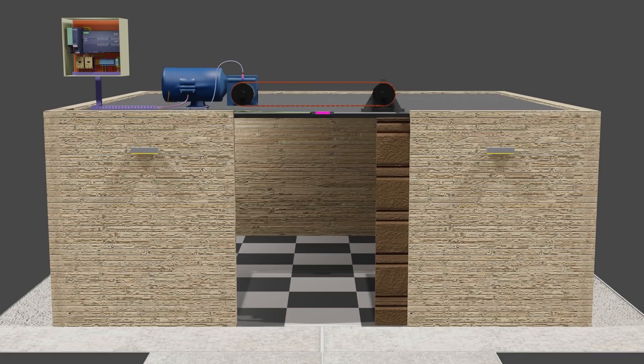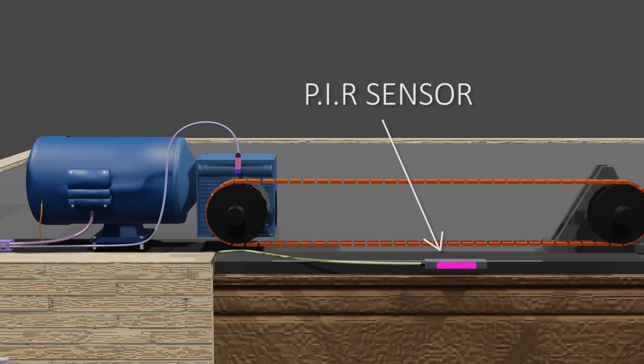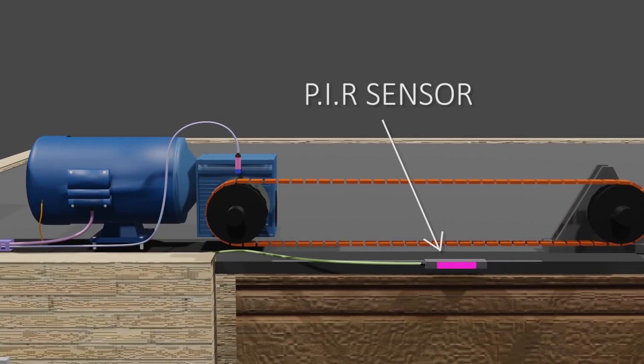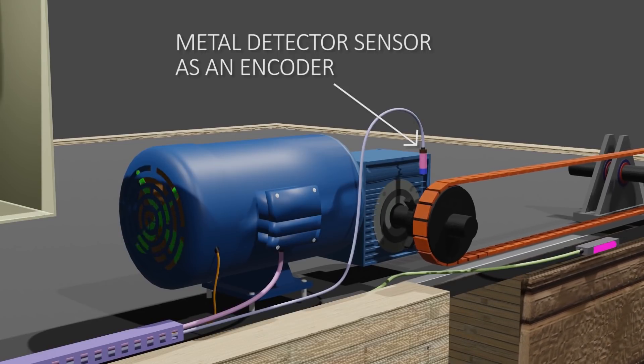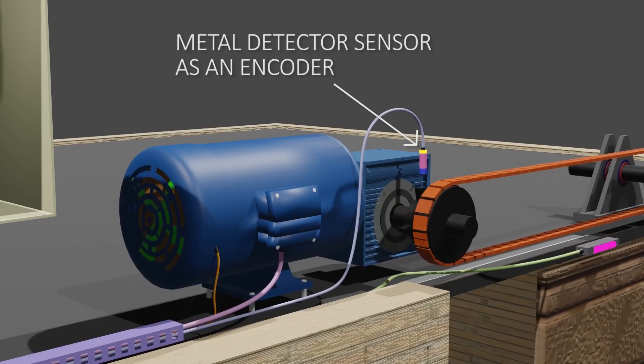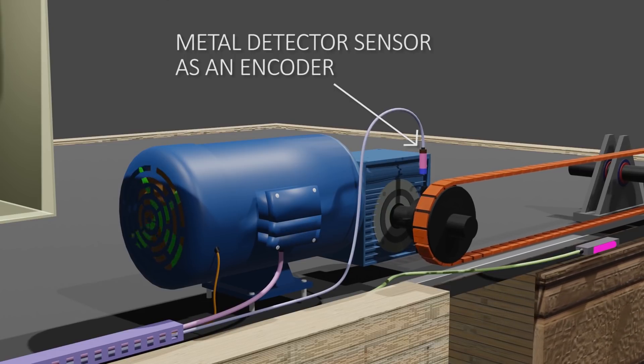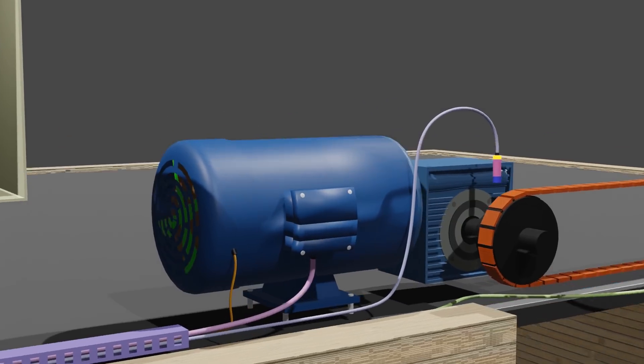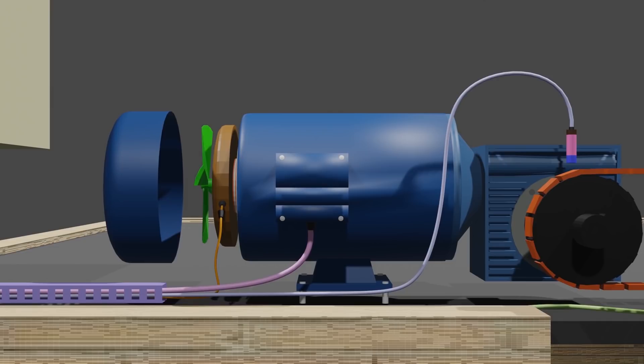Let's quickly see the setup for today's tutorial. First, we have a PIR sensor which will be used to detect living bodies in front of the door. Next, we have installed a metal detector sensor on the gearbox — it will detect the teeth of the gear and give output pulses to the PLC input, so the sensor is working as an encoder to track the current position of the door. Next, we have a three-phase motor to open and close the door. This motor has a brake disc which is used to suddenly stop the motor at specific positions.